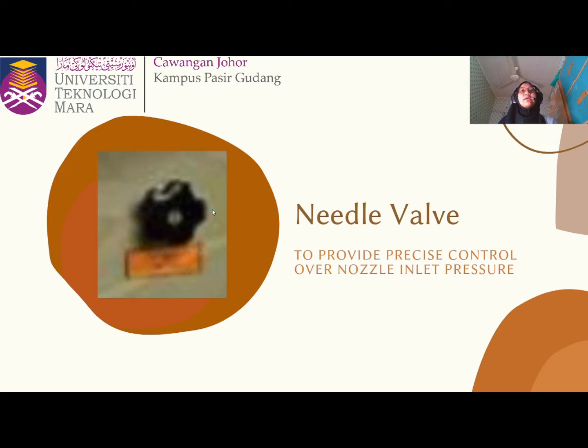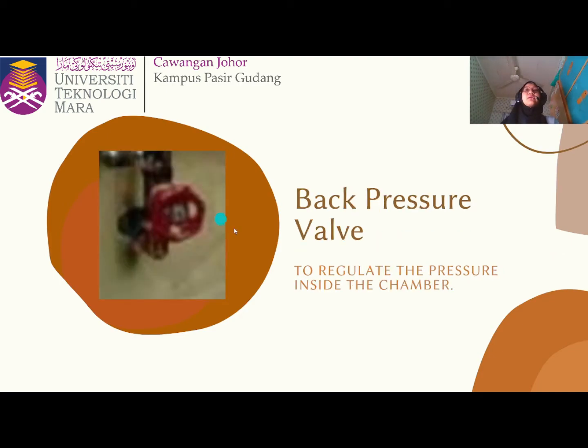Needle valve, to provide precise control over nozzle inlet pressure. For the back pressure valve, it is used to regulate the pressure inside the chamber.